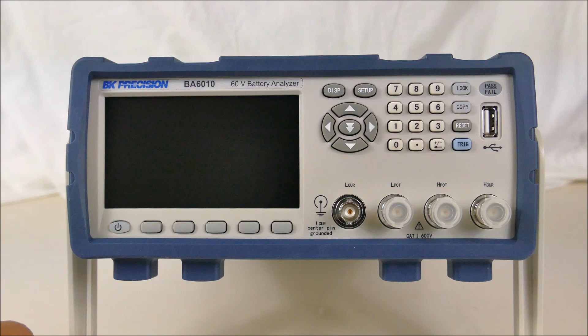So there's high impedance to the potential measurement here, and the current being transmitted through the leads doesn't affect the voltage measurement. So there might be IR drops in the leads, but the potential measurement doesn't see those because they're not in the circuit that's being measured. So that's the front panel.